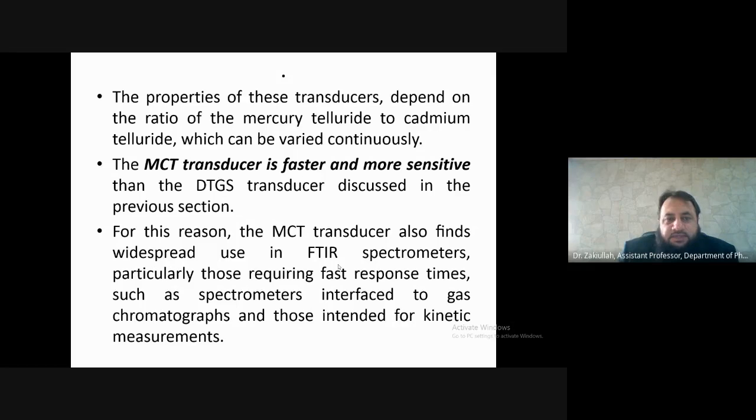transducers. So for this reason, the MCT transducers also find widespread use in the FTIR spectrometers, particularly those requiring fast response times, such as spectrometers interfaced to gas chromatographs and those intended for kinetic measurements. So in these types of studies, these MCT transducers are more desirable.